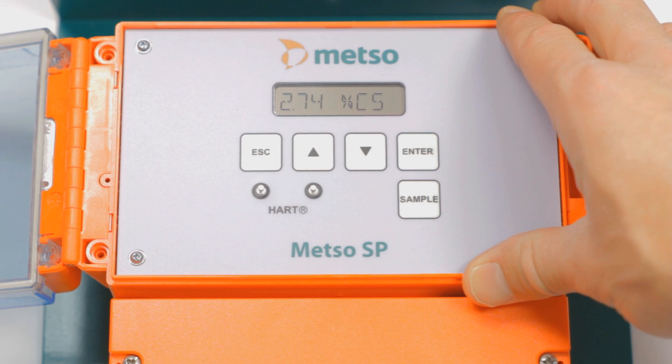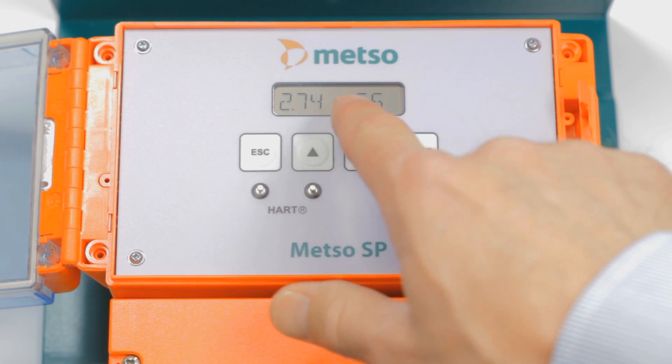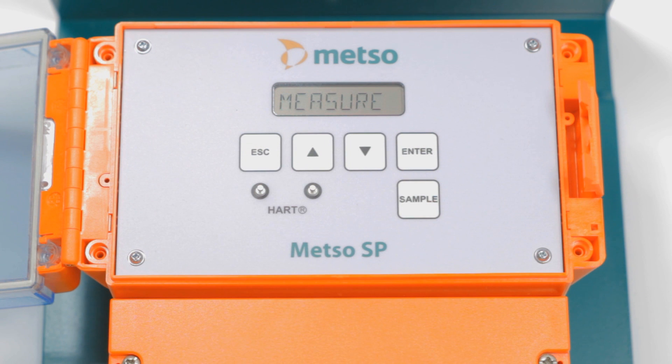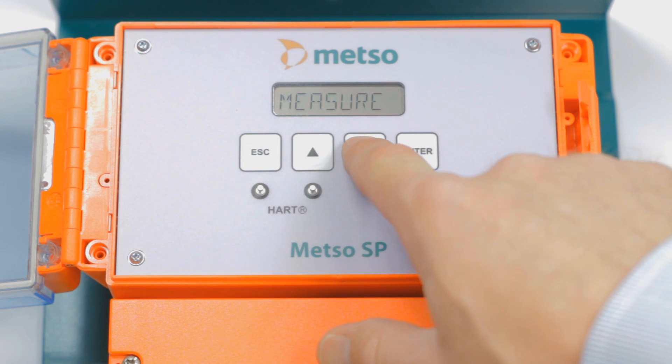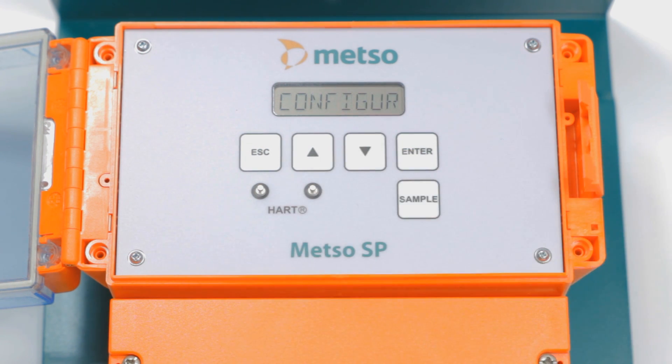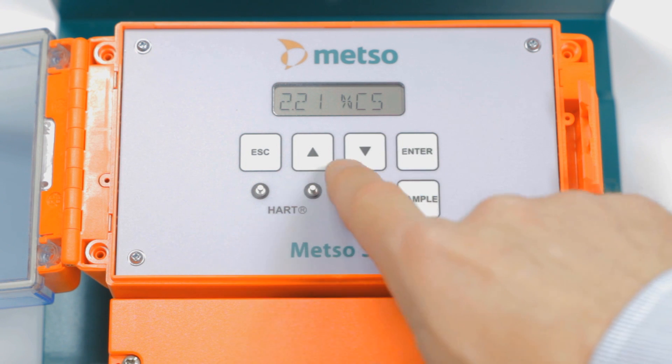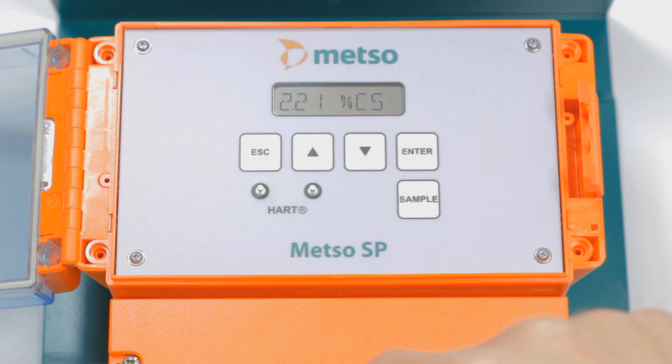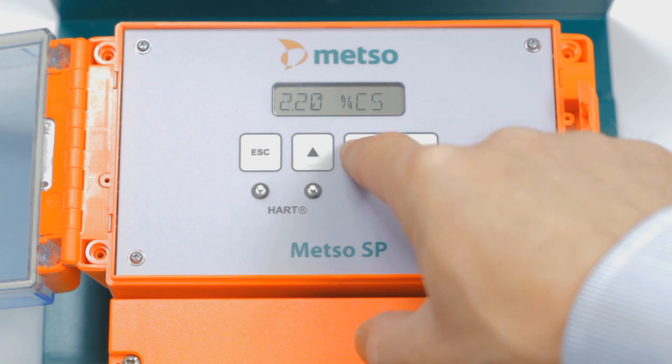Typically, when you approach the display in the mill, it's going to be measuring consistency, which is under the measurement menu. As we talked about, we're going to go to the configuration menu to set the transmitter up. We're going to hit enter. And we're going to hit enter again, lower range. And we want to set that lower range at 2.00, so we just hit the arrow down button. And hit enter to accept it.